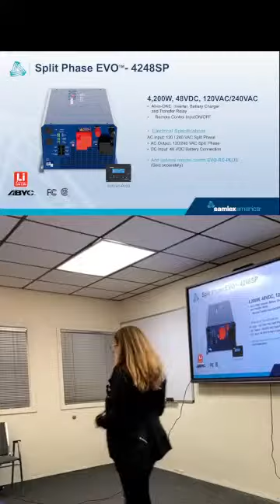As I said, it's very fast. Any problem with the power sources, the unit will make adjustments to properly charge what needs to be powered. In certain areas - I'm not sure if this happens in the US - sometimes it's not that you lack power, but that the voltage received isn't proper. When that happens, you can program the unit to switch to the battery bank, avoiding low voltage damage to whatever is powered, since it switches to the battery bank and charges properly, avoiding damage or poor performance.